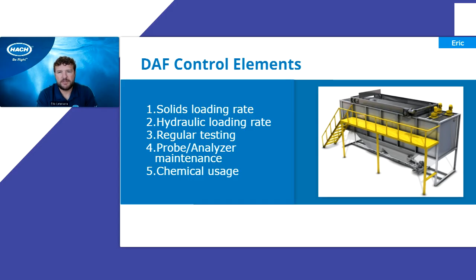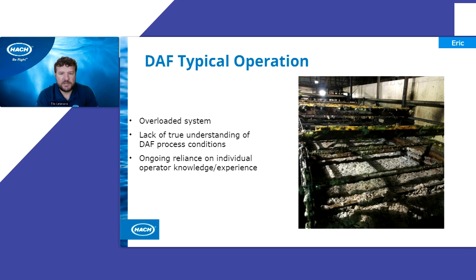Chemical usage. So oftentimes chemicals are dosed at this point in the process. So whether it's a flocculant or a coagulant that's being added to create larger particles to have some float up and be skimmed off, or settle to the bottom, which can be captured as more of a cake or a sludge cake. So typical operation. This is fairly typical going into a lot of industrial plants: there's an overloaded system, which means they're really trying to push their system because they're trying to get as much treatment as possible, which can lead to a number of different problems.